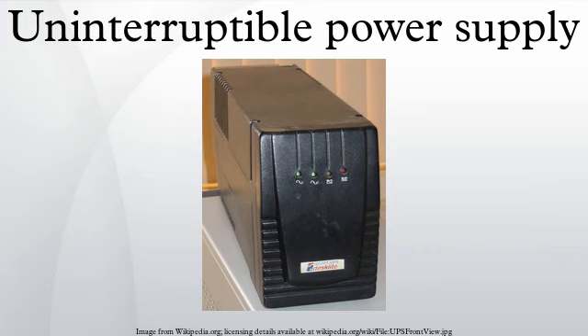Measuring efficiency. The way efficiency is measured varies, and there are a number of reasons for this. Many UPS manufacturers claim to have the highest level of efficiency, often using different sets of criteria in order to reach these figures. The industry norm can be argued to be anything between 93%-96% when a UPS is in full operational mode, and to reach these figures companies often put their UPS in an ideal scenario. Efficiency figures on site are often much closer to the 90% mark, due to varying power conditions.